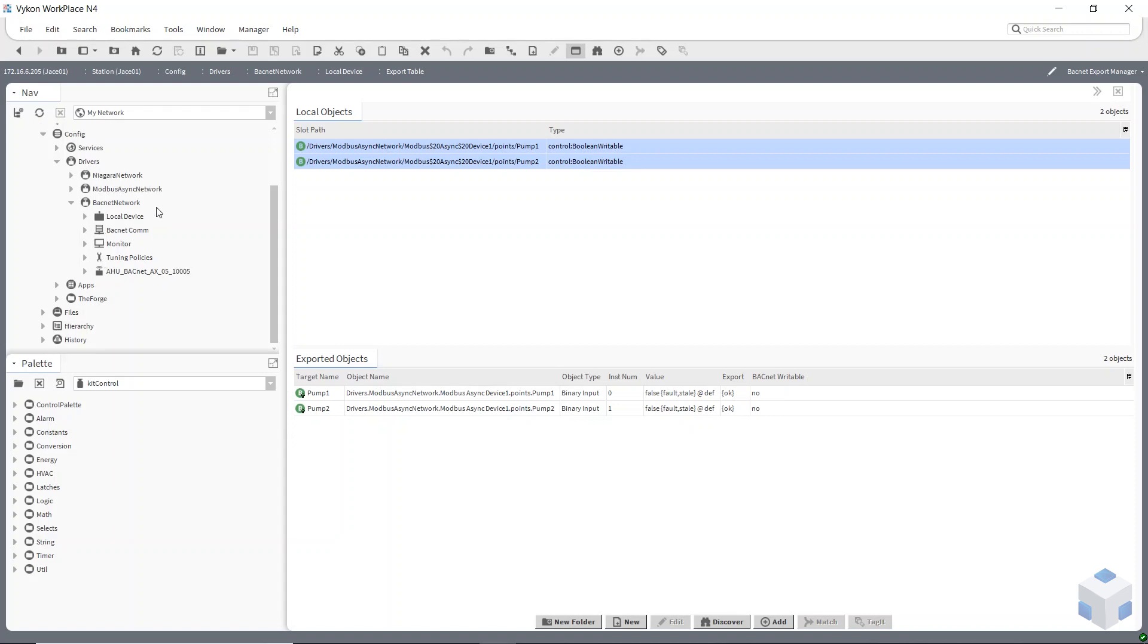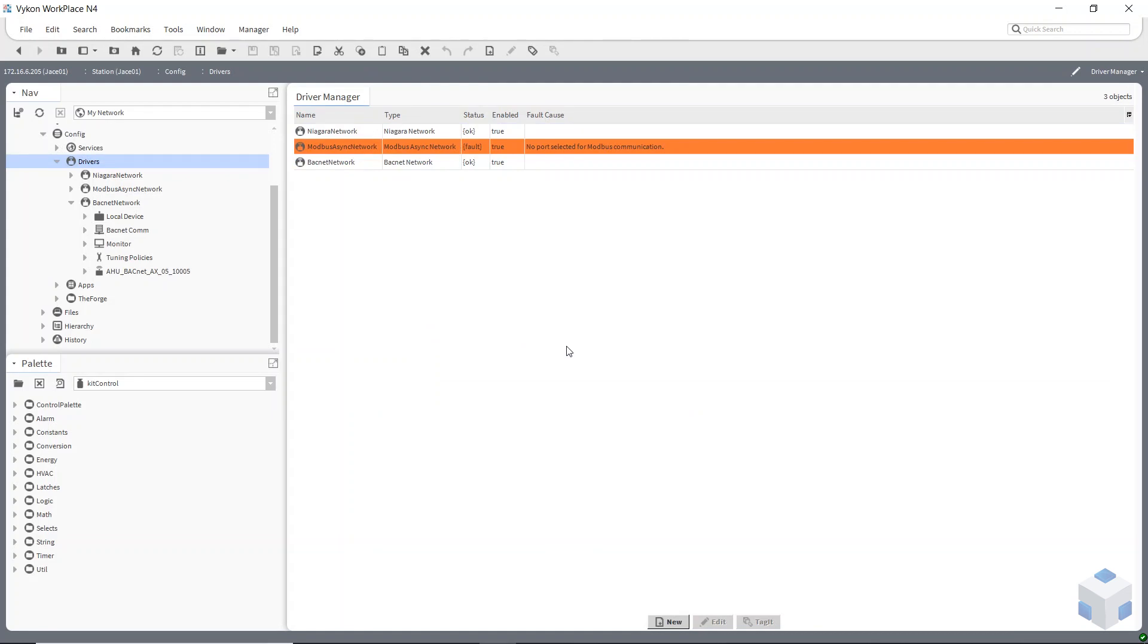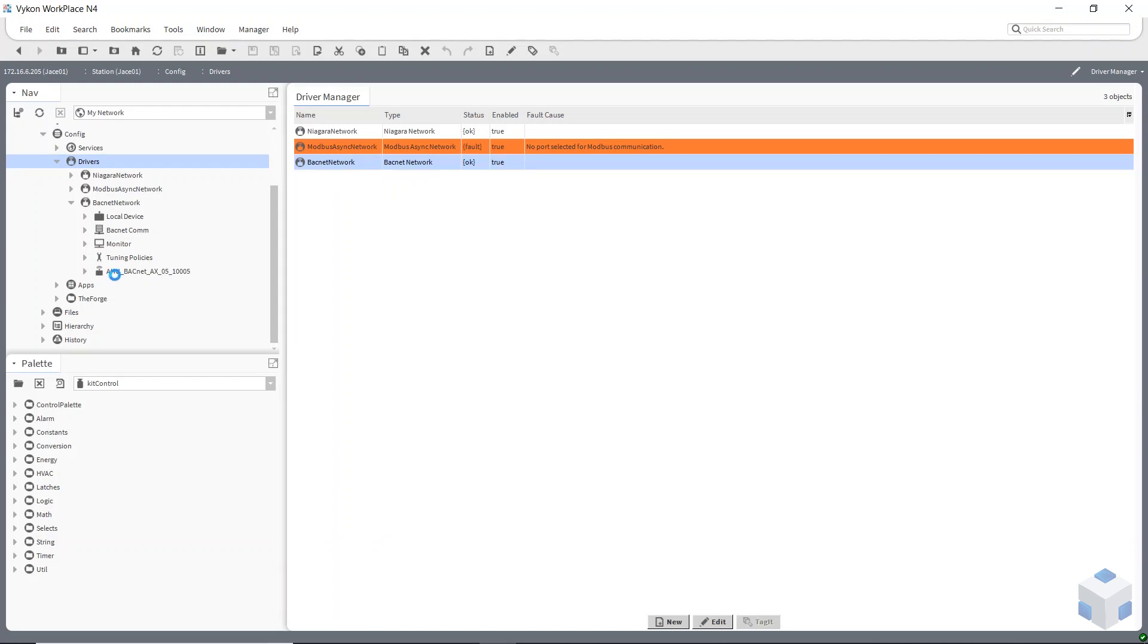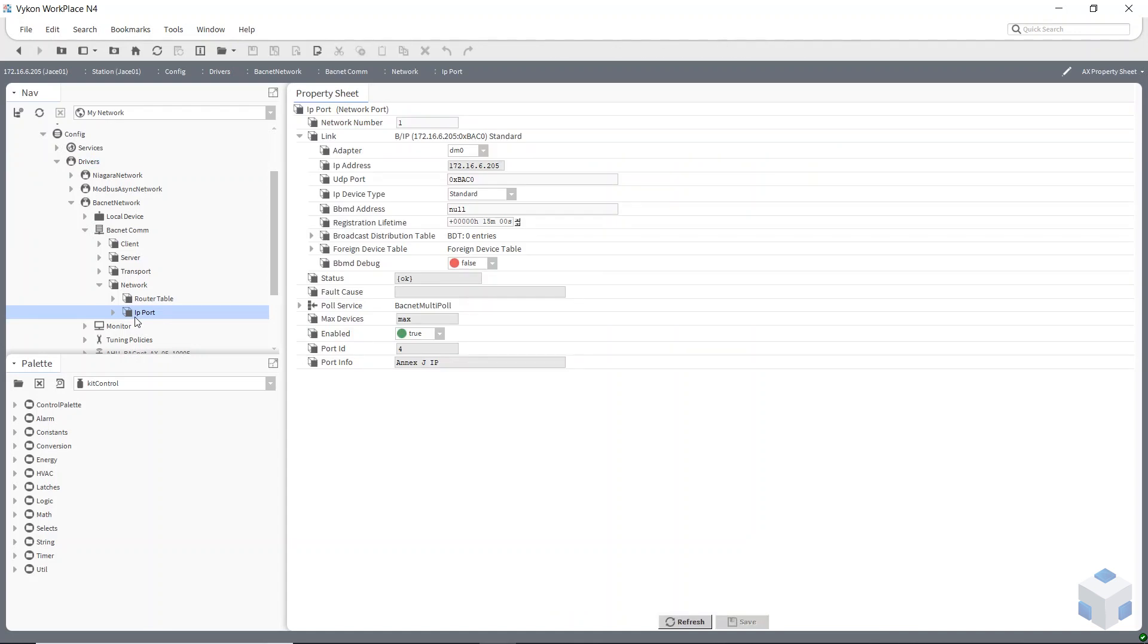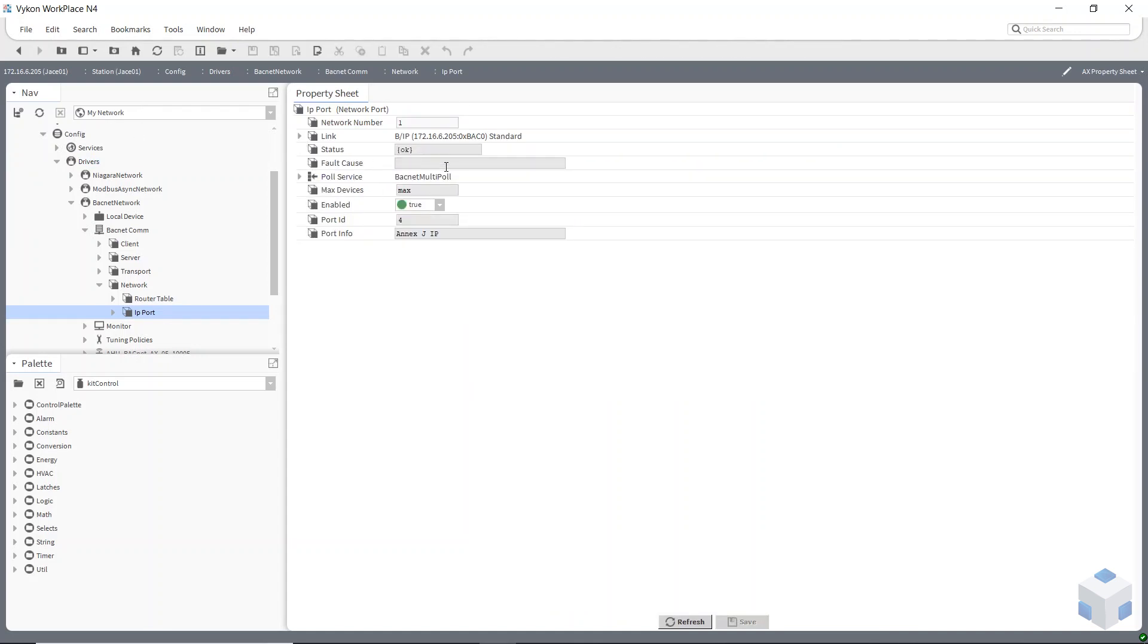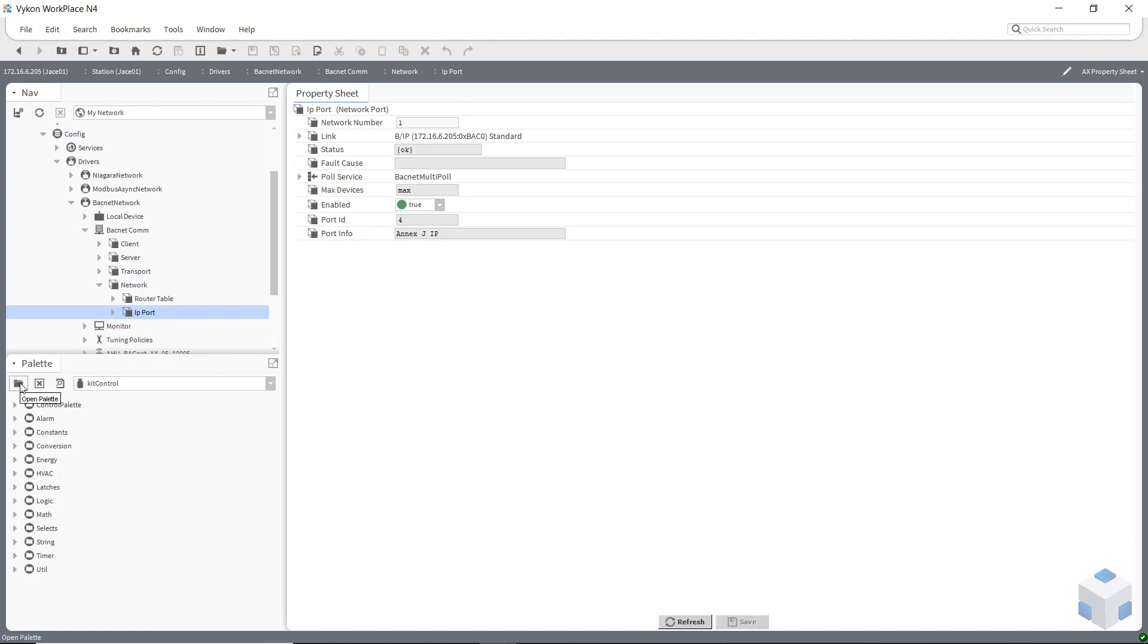Okay so one more final thing just to show you quickly because it's actually a question that comes up a lot in tech support is how do I add a 485 network, a BACnet network. So you don't do what you might think and add another BACnet network. You actually go into the BACnet network you've created already which defaults to IP. That's why when I set this IP one up I already had IP port on there. So if I then go back to my area where I saw when I set my IP port up which is underneath my network in underneath BACnet com, you can see here I've got an IP port already set up there which I just already set up.